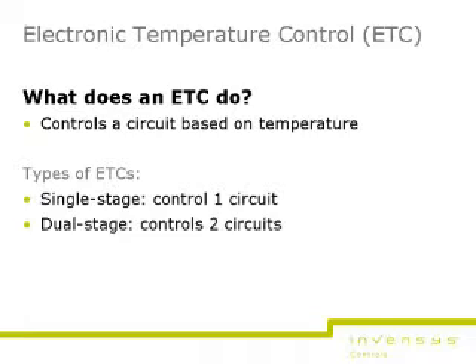What does an electronic temperature control do? There are two models for controlling machines: the single-stage model and the dual-stage model. The difference is that the single-stage has one single-pole double-throw switch to control. The dual-stage control has two single-pole double-throw switches to control two circuits. These switches, also known as relays, can turn on or off a wide variety of machines, depending on the maximum current ratings.